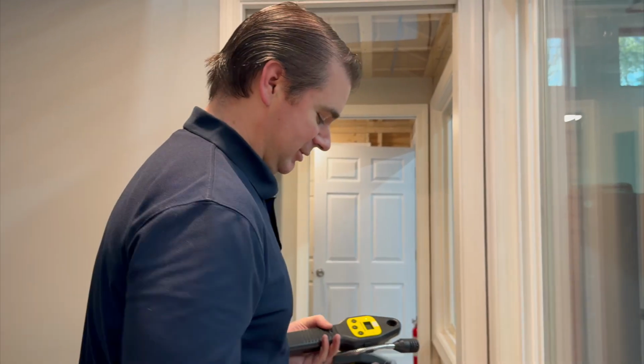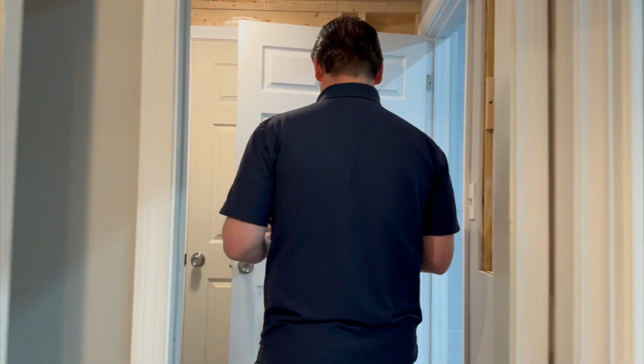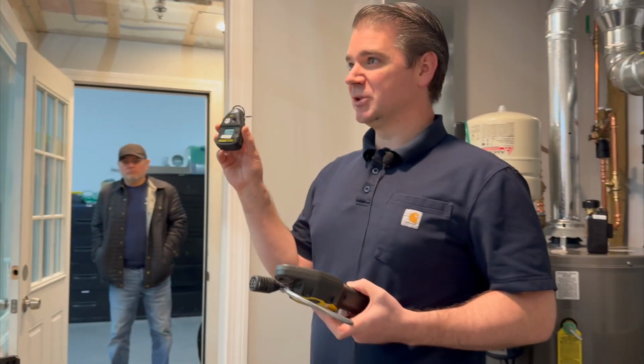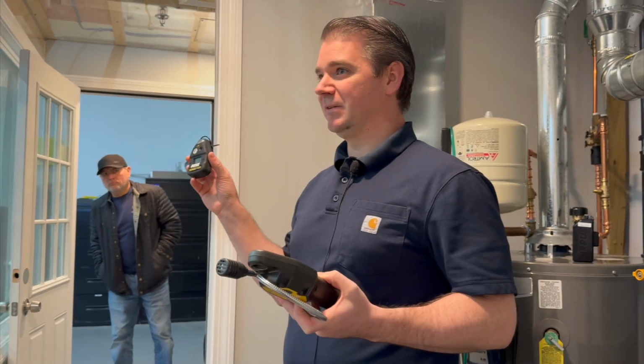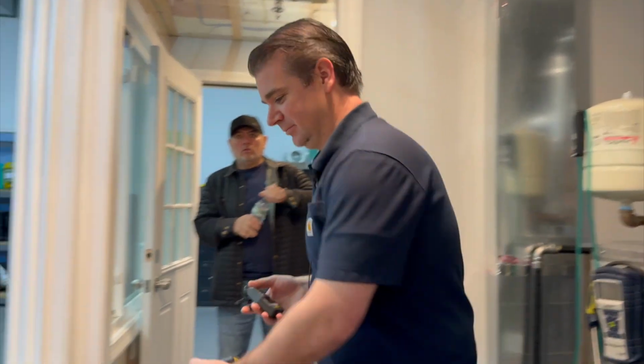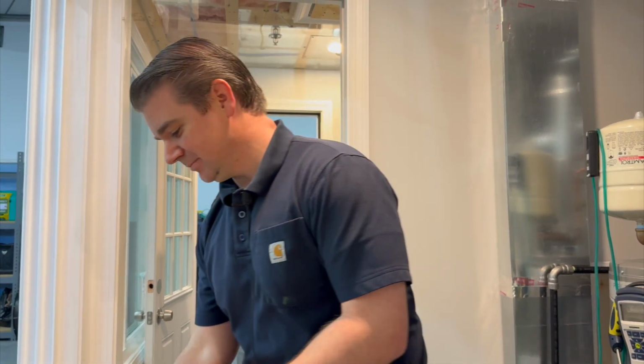Then I'm going to take just 30 seconds to walk around the house with my combustion gas detector and my CO monitor. I'm looking for ambient gas and I'm looking for ambient carbon monoxide. With my CO monitor, it's reading 0 parts per million. No actions required. It's safe for us to continue our audit. With my gas leak detector, it says 0 parts per million. That's less than 10% of the lower explosive limit. It's safe for us to continue our audit. Put the CO monitor back in my belt so I don't lose it.